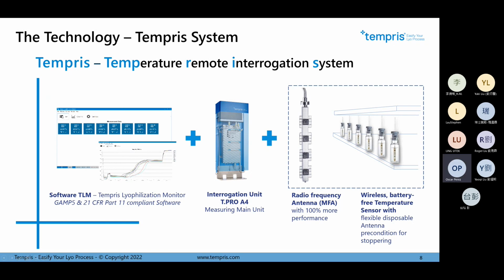Then we have the software. The licenses are installed in the main interrogation unit, and then we have the visualization software, which has to be installed on an external computer or the freeze dryer control system PC, with different licenses depending on the application. Of course, we have different licenses for the number of sensors, for the number of antennas, for 21 CFR Part 11 compliance, etc., and to monitor the temperatures in real time.